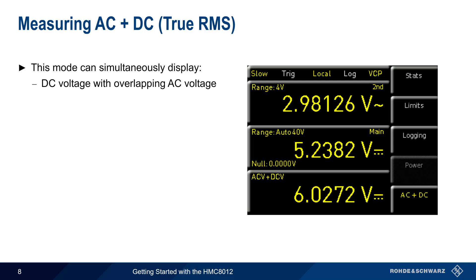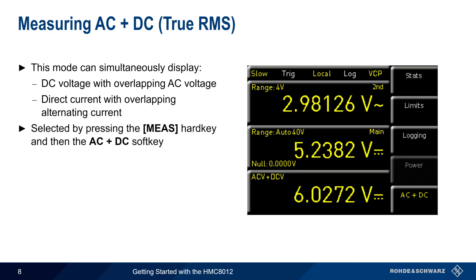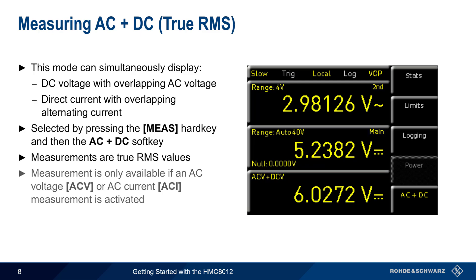AC plus DC mode can simultaneously display DC voltage with an overlapping or superimposed AC voltage, or a direct current with an overlapping alternating current. This mode is selected by pressing the measure hard key and then the AC plus DC soft key. As with other AC measurements on the HMC 8012, these are true RMS measured values. Note that in order to select this mode, an AC voltage or AC current measurement must be active.